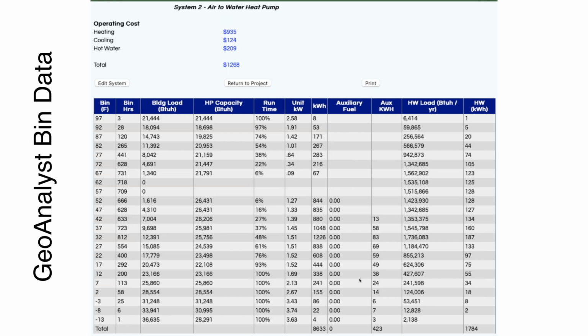And when we look at the efficiencies and capacities of this Advantage air-to-water heat pump, it really shines in that 20 to 50 degree range. It's not bad even all the way down to -13. It still has a COP of around 2. But where you're going to get most of your operation, the COPs are in the 3 range. And so this is really important to look at the operating costs, but also it gives you a pretty good feel for where backup heat comes in, how the unit's operating, that kind of thing. So we use bin data a lot, not just on air to water, but on geothermal, so we can get appropriate sizing. And that's all part of this GeoAnalyst software.